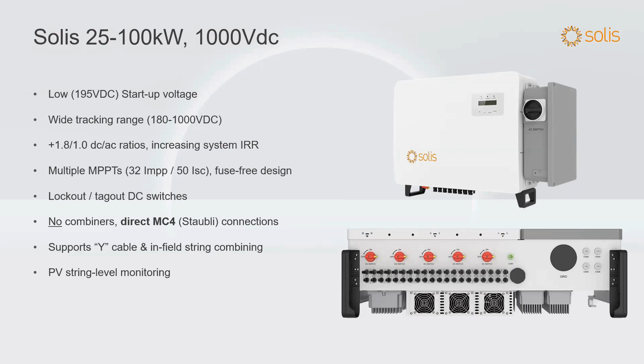480 high input, again, terminals on the bottom. And again, you can see those lockout, tagout DC switches. Kind of a unique feature. You also might see there's fans down there as well. These are just supplementary to blow over the heat sink. So if you are at, let's say, a 15-degree mount on some flat roof, these fans will come on when necessary. They don't run all the time, just when necessary. And should one fail, gets a lizard or some grass or something in there, it doesn't shut down the inverter, but you will get an alarm that one of the fans is down, and you can replace that at your leisure.